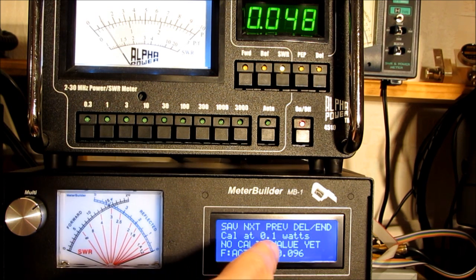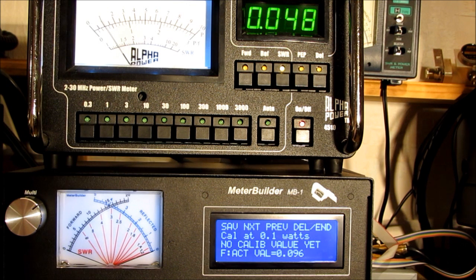Okay, it tells me that the next value that it wants me to calibrate is at 0.1 watts. So let's see if I can dial in 0.1 watts. The RF controls on these rigs are pretty touchy, especially at the low powers, but that's pretty good. 0.099, and again I'll dial in 0.099 on line 4 of the LCD so that the calculation will be more accurate. Let me go ahead and hit the save. If I wanted to jump all the way up, let's say to 5 watts, okay, I crank the power up to 5 watts on my reference meter, as close as I can get it.